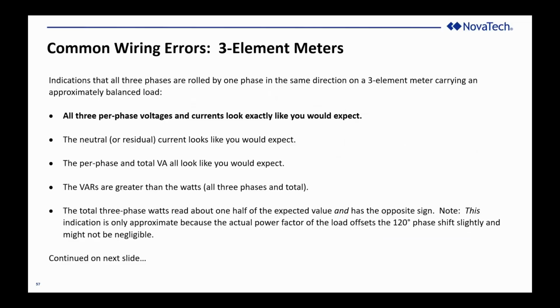Now what happens if we rotate the phases? Rotating the phases is a lot of fun. It's different from inversion, you don't have 180, now you've got a 120 degree phase shift. Now the watts and the VARs do different things because the effect of a 120 degree phase shift on the sine and the cosine is completely different. So this is where it gets a little more interesting, and it's more common. It's very easy to swap an A and a B voltage connection terminal on a meter than it is to invert a polarity or the like.